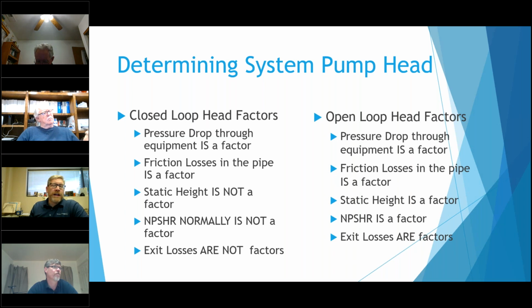On open loops, you still have to worry about the pressure drop through the equipment, friction loss. But now, since there's a break in there, and the pump does have to overcome that break, you do have to worry about the static height, because if that water turns off, it's going to seek a certain level, and that pump then has to push that water to the top. So you do have to make sure the pump is big enough to get it up to the height of the top of the system. The net positive suction head is going to be a factor.